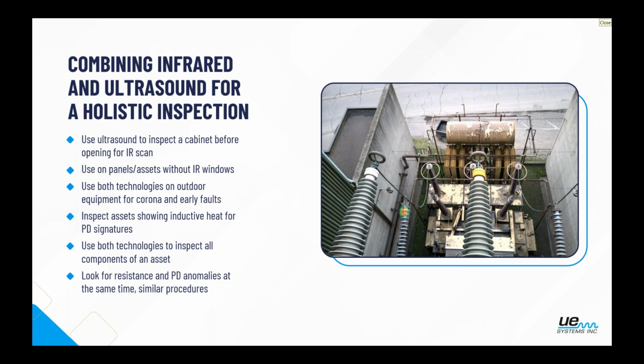So now that we've looked at specific assets, where would I use ultrasound versus infrared and vice versa, when we're doing them together, there are very specific applications where it's a huge benefit. I've just listed out a few of them here. As earlier, listening around the outside of a cabinet before we open it up, even if we're in the correct PPE, I don't think anyone wants to test the threshold of what that equipment can actually handle. And it's designed to keep you alive, not necessarily keep you comfortable if there is an event that happens.